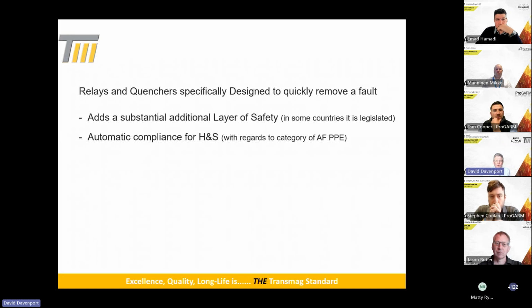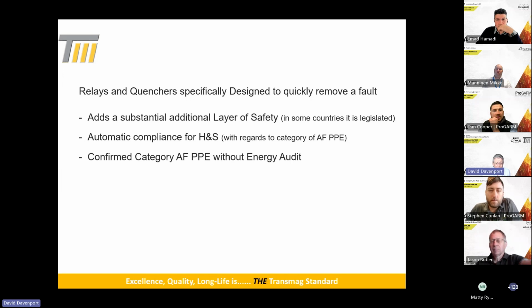It gives you automatic compliance for health and safety with regards to the category of arc flash PPE. It will dictate to you exactly what the calories per centimetre squared are, both at the working energy level and also at the boundary levels. Confirmed category without an energy audit. Look, we carry out energy audits ourselves, arc flash assessments, arc flash studies, and they're well worth having, but they are an MOT. The minute that you change anything within the infrastructure, it's outdated really, and it needs to be done every 5 years, and not every organisation can afford the thousands of pounds that they actually cost. So this is a good way of making it a standard that does control the calories per centimetre squared.